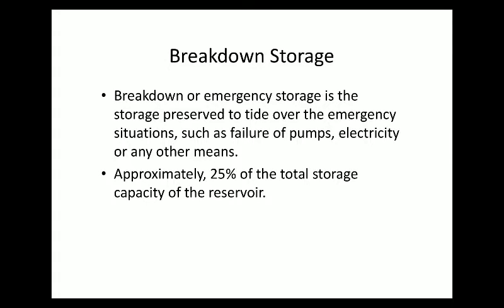And the next part is breakdown storage. Breakdown storage is for emergency purposes. If there is any kind of emergency situation, such as failure of pumps, failure of electricity, or any other means, then a certain percentage of water should be stored in the reservoir, so that the city might not get trouble for water supply. That percentage is approximately 1/4 or 25% of the total storage capacity of the reservoir. I will show you the calculation in the later slides.